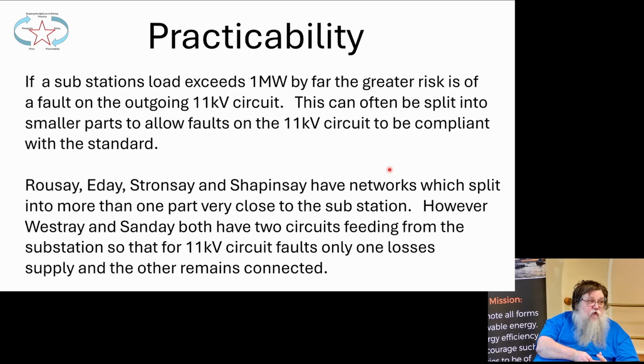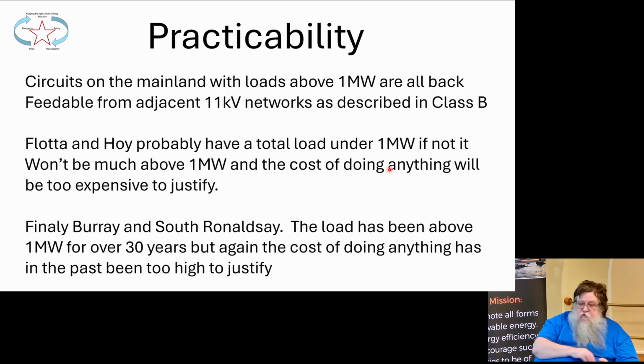Westray and Sanday have 2 circuits feeding from the substation, so that for 11 kV circuit faults, only one loses supply and the other remains connected. And Westray and Sanday are the ones that have got the biggest loads in Orkney. Westray feeds Papa Westray as well, and Sanday feeds North Ronaldsay as well. So on the mainland, circuits with loads above 1 megawatt are all backfeedable from adjacent 11 kV networks, as described in the Class B section that I went through.